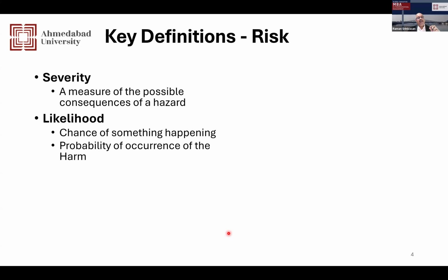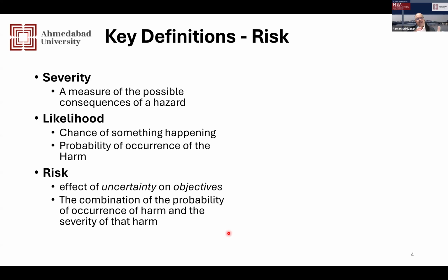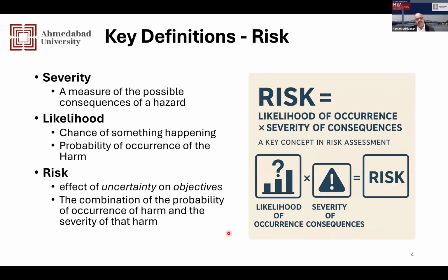Now, when you combine the severity and likelihood, you have the risk, and the risk is nothing but the effect of uncertainty on the objectives. Here we are specifically talking about the objective of the health of a patient. Uncertainty is there all the way, when you start developing the product, manufacturing the product, reaching the product to the patient, and when the patient is using it. All the way through there are hazards. Now, what is the likelihood of those hazards coming along, creating some hazardous situations and resulting in a risk, right? So the combination of the probability of occurrence of harm and the severity of the harm, that is a risk. This is one of the most basic equations in risk: the likelihood of occurrence and the severity of the consequences.